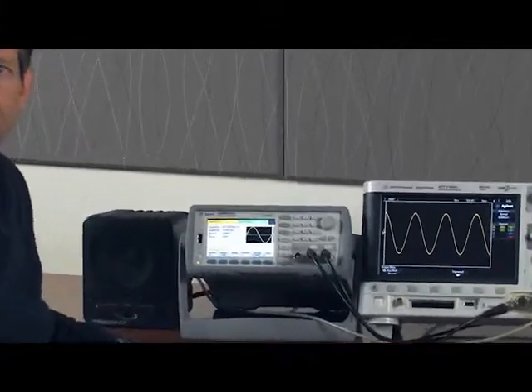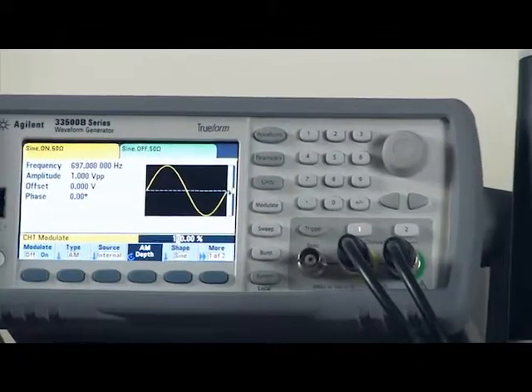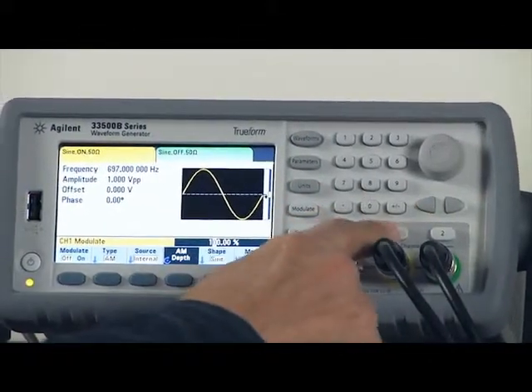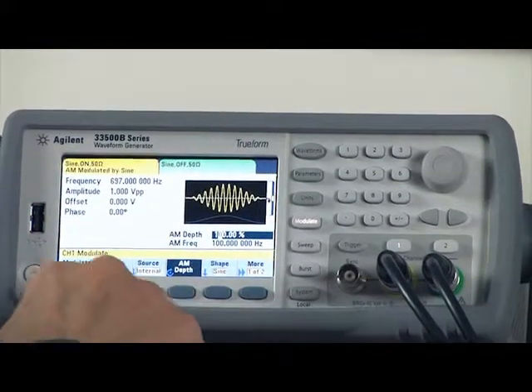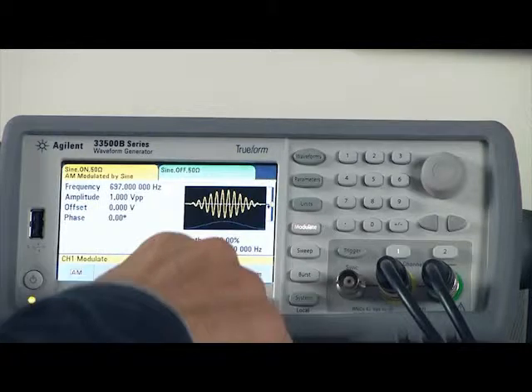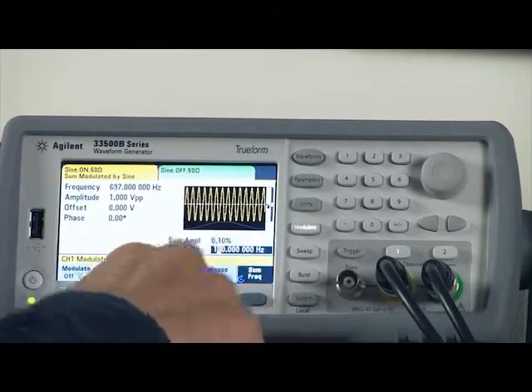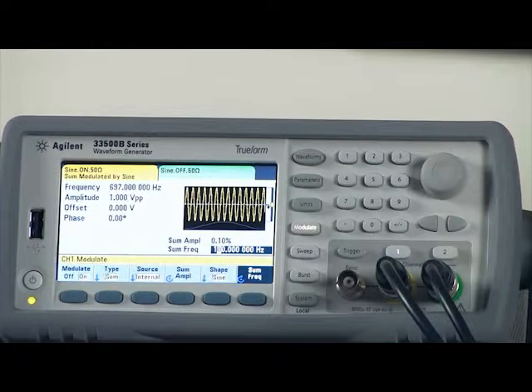Let's now add the second tone, which is at 1209 hertz. We do that with the modulation menu. There's a modulation type called sum.